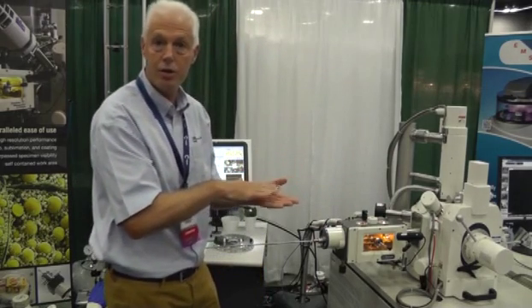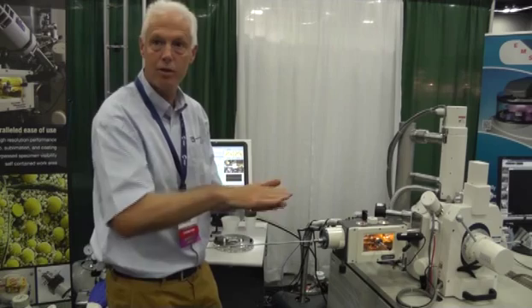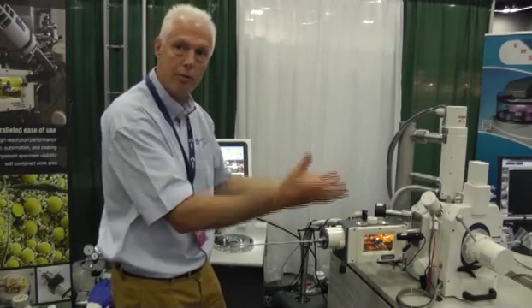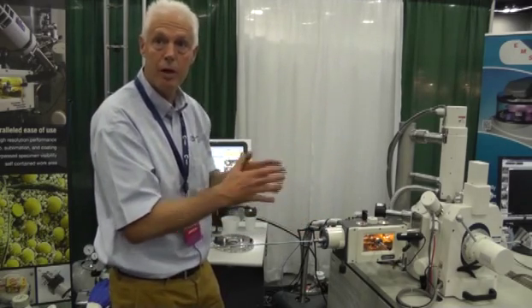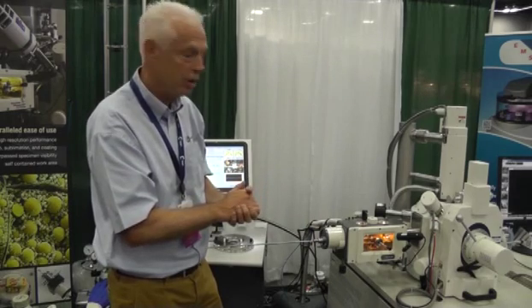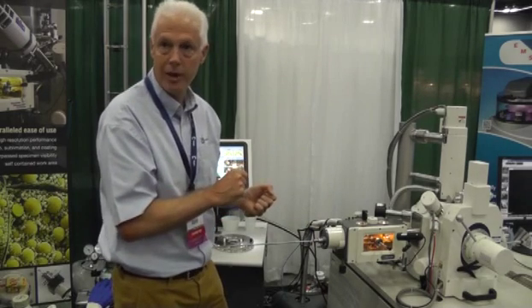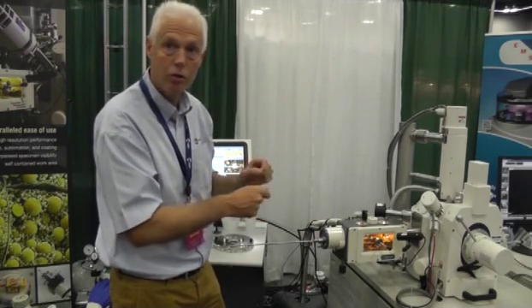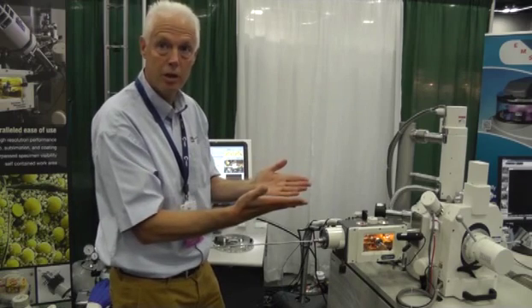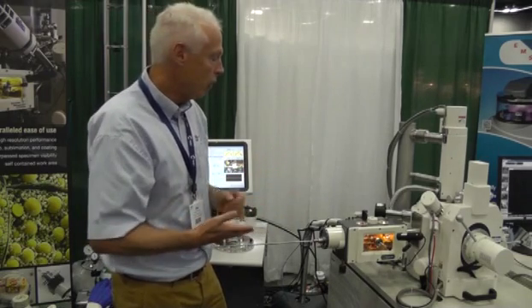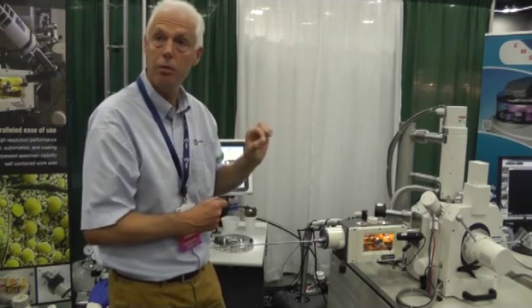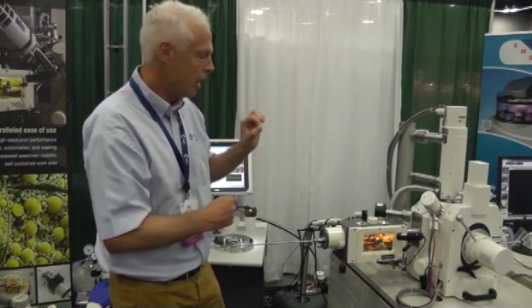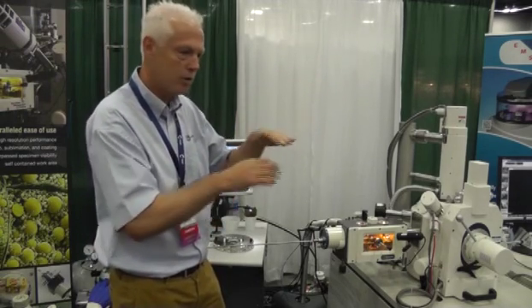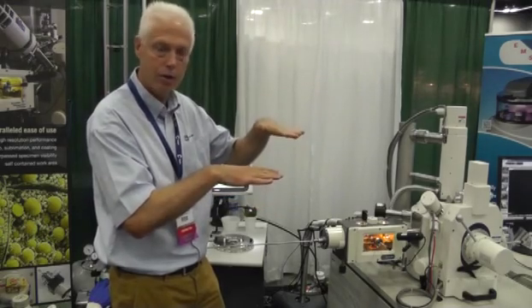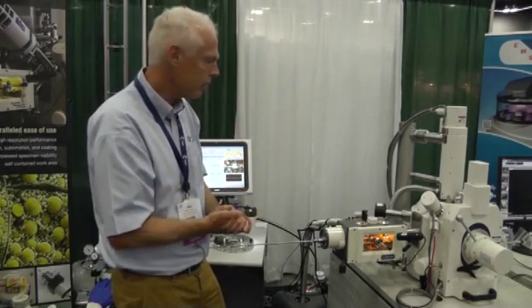Normally we set the temperature of that between -130 and -160. We have cold traps all around to ensure that there are good conditions inside the vacuum. And we can do a number of things here. We can fracture, cold fracture, to reveal internal information. We can also sublimate by controllably raising the temperature for a limited time to remove surface water or ice.